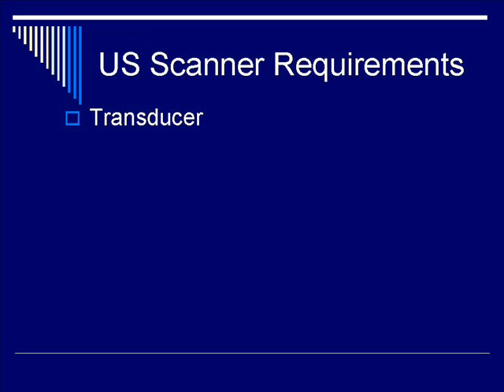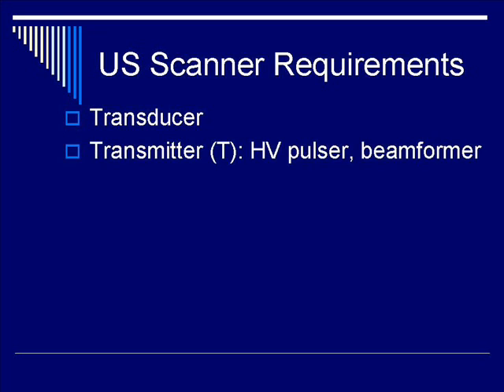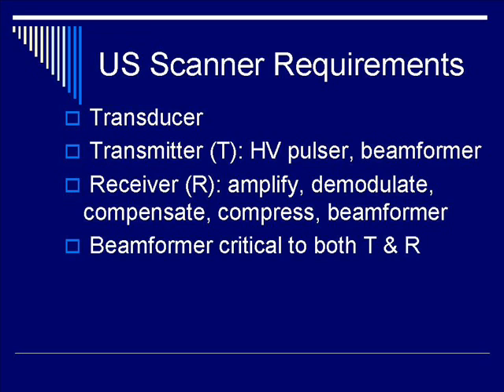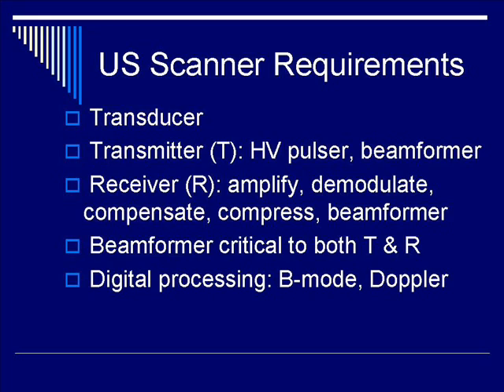Now let's move on to ultrasound scanner requirements. This includes a transducer, a transmitter feeding into a high-voltage pulser and a beamformer, and a receiver whose job is to amplify, demodulate, compensate, compress, and beamform. The beamformer is critical to both transmit and receive. The digital signal processing aspect of the system processes B-mode and Doppler measurements.